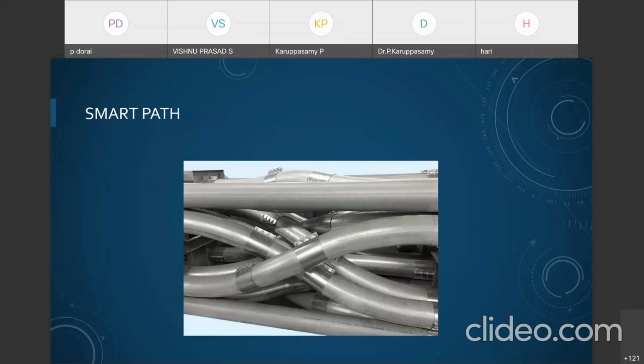For example, if the 5th floor is the service floor and we need to send the capsule to the 11th floor, by the vacuum process it will go to the 5th floor and then divert to the 11th floor by pressure. This smart path converts and diverts the capsule to where it wants to go and where it needs to be sent. This is the smart path, and we can see the diverter mechanism here.